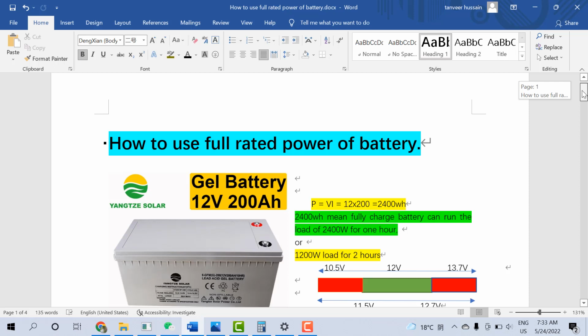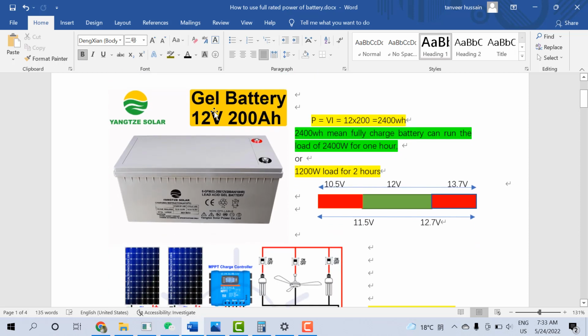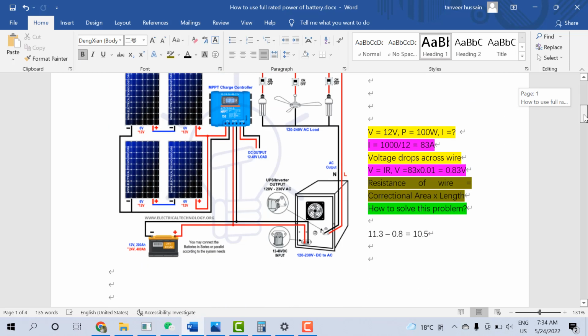So the first problem: if you have a battery, for example 2400 watt hour, and you run a 1200 watt load, it should work for 2 hours. But when you use the system, sometimes it only works for 50 minutes, 40 minutes, or 1 hour. That's not according to the calculation. So what is the root cause of this problem and how can we solve it? I'll explain this in detail later.